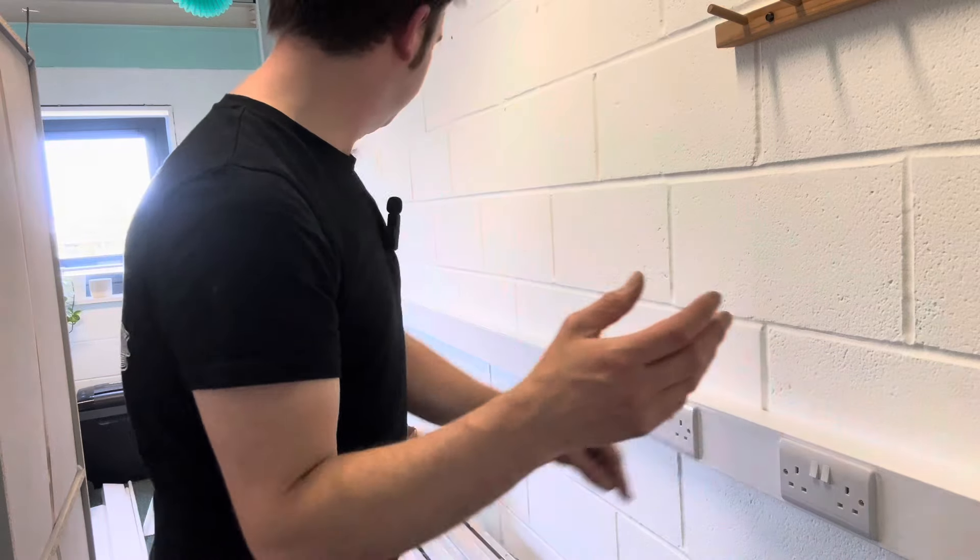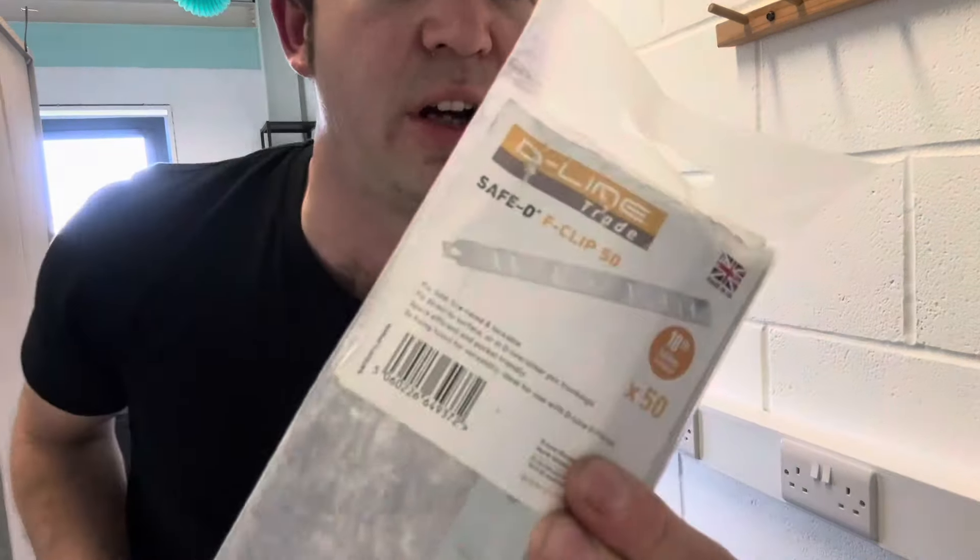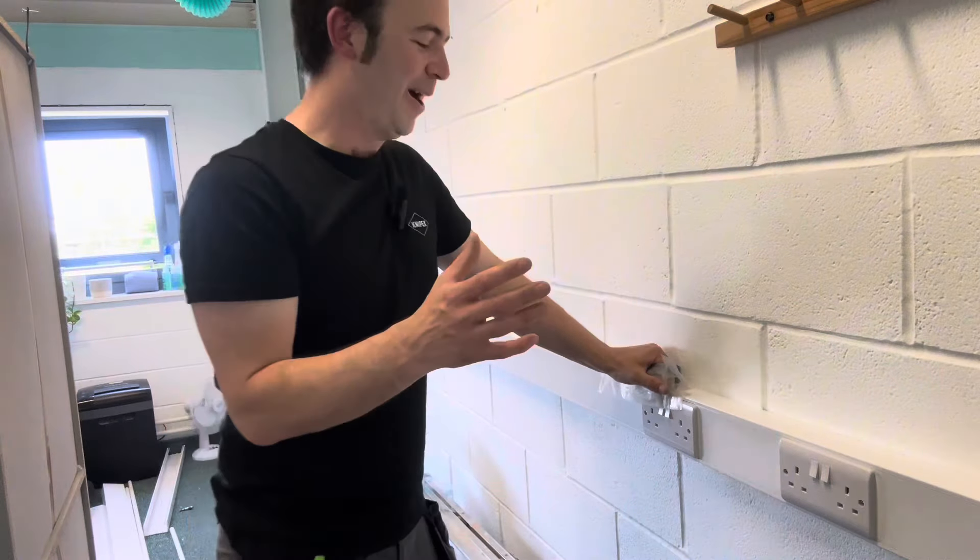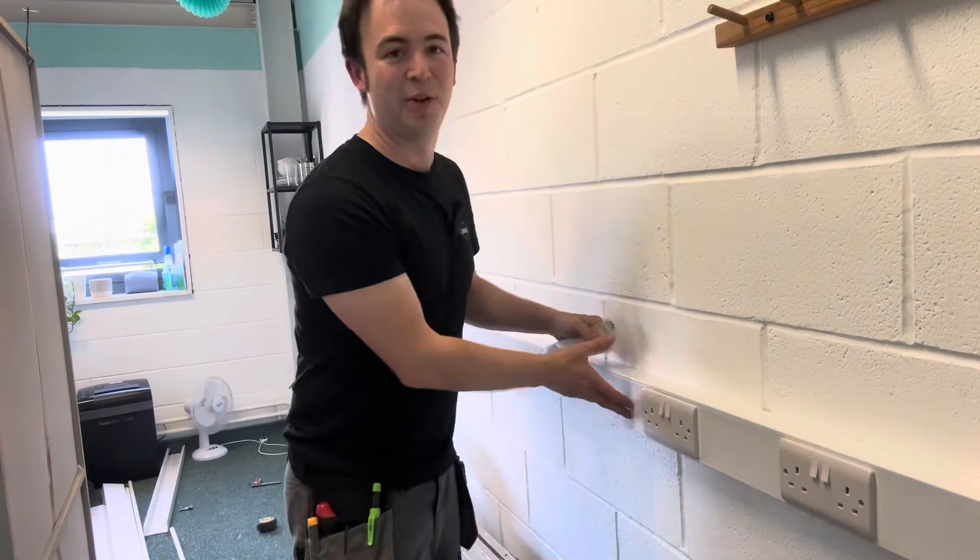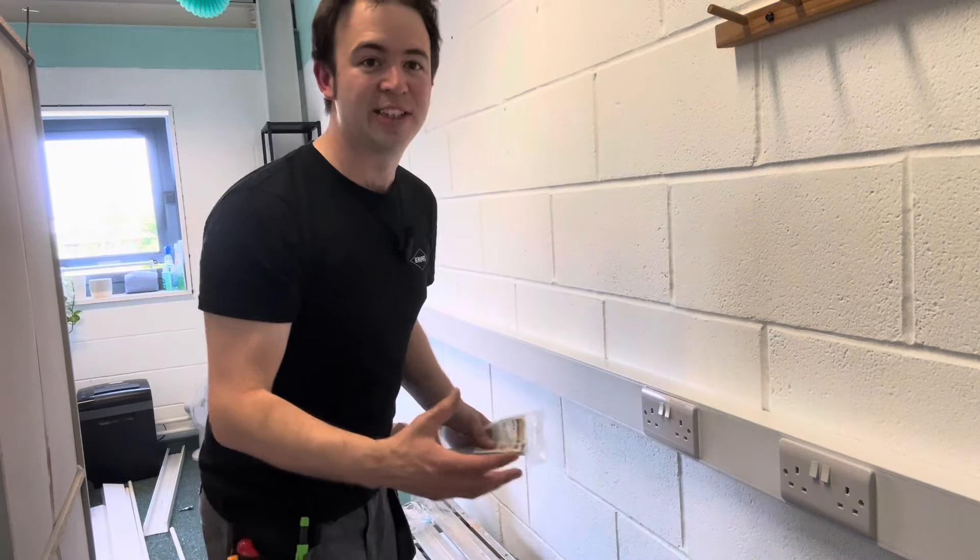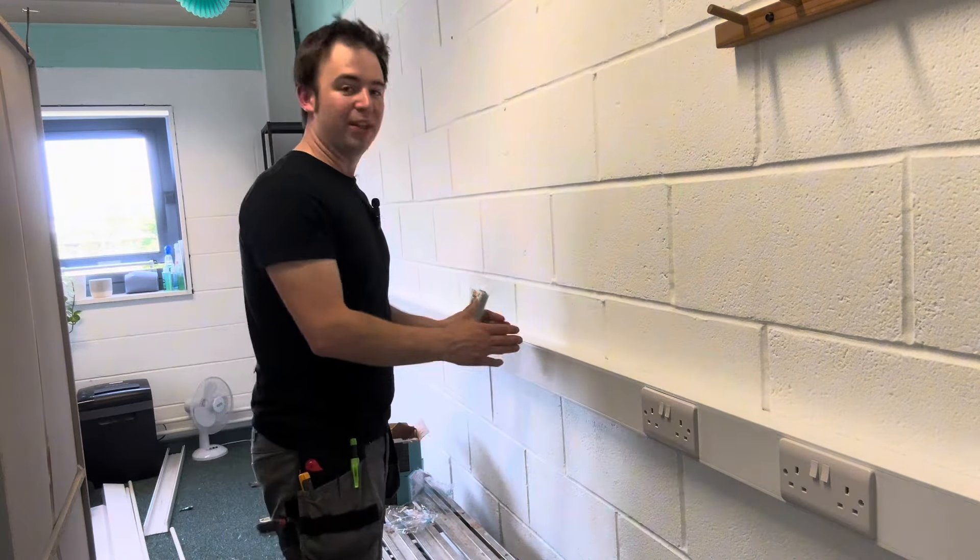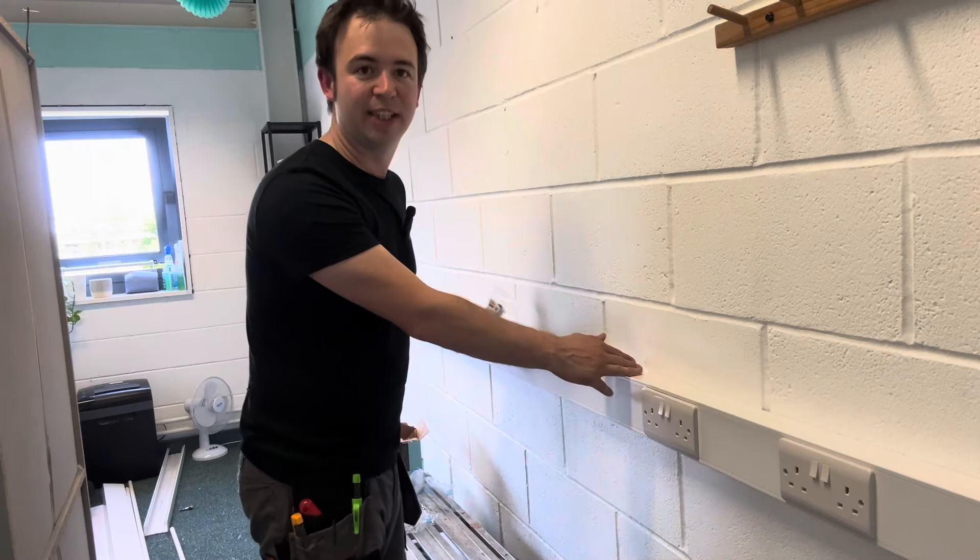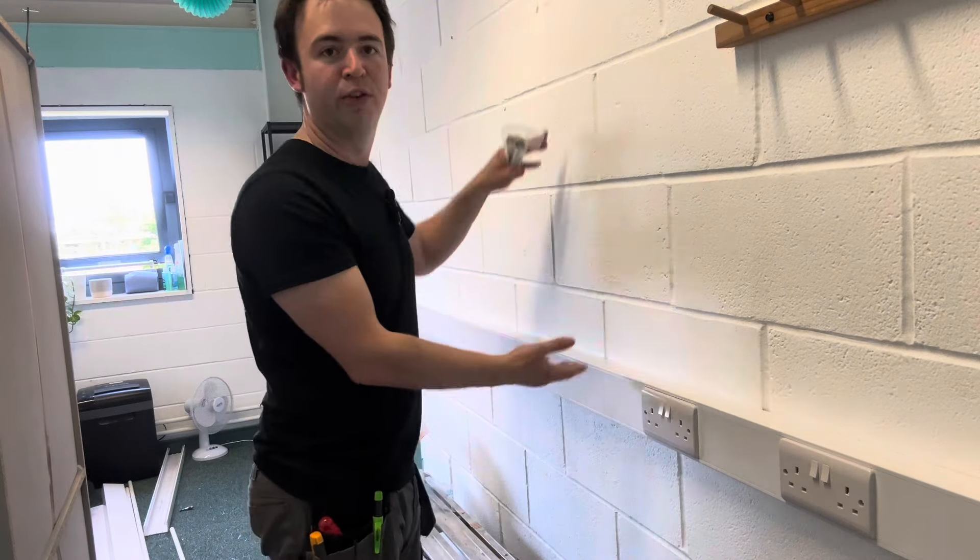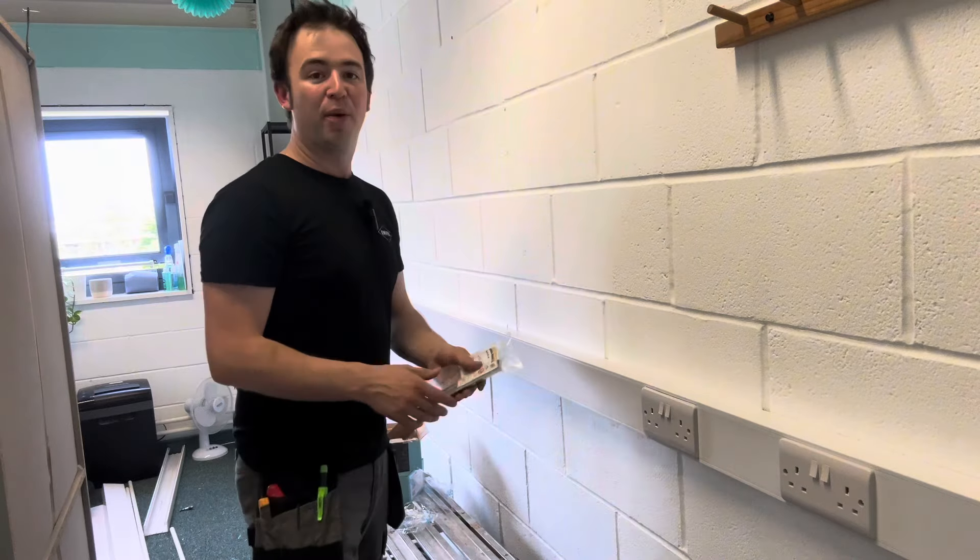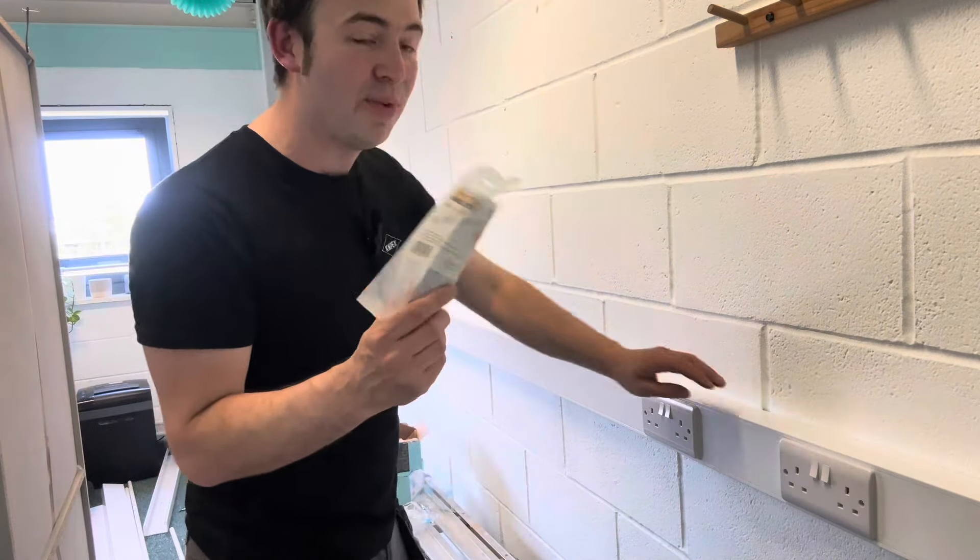I've got some fire clips, some of these safety line fire clips inside the trunking. Now a little bit of common sense has to be applied here because this is only a meter from the floor. I know the regs and on-site guide both say about the distance of fixings or the spacings of fixings, and there's a different measurement for when it's horizontal or vertical and conduit and trunking. However, it's always been a grey area, especially even when the regs changed.